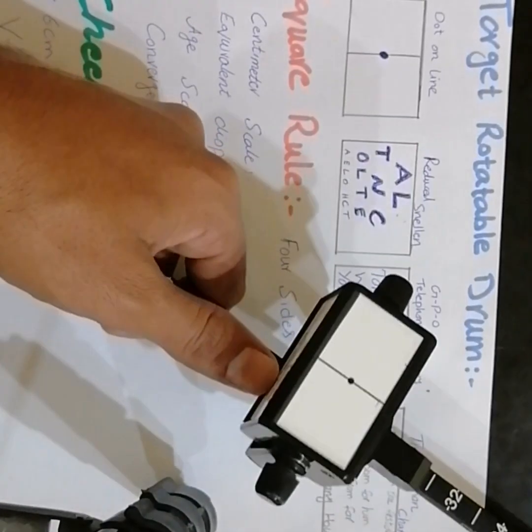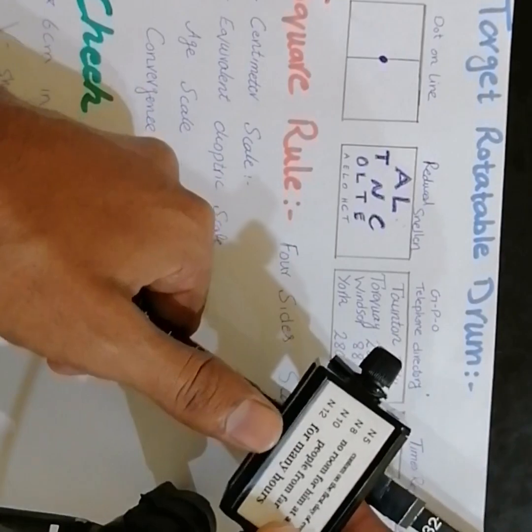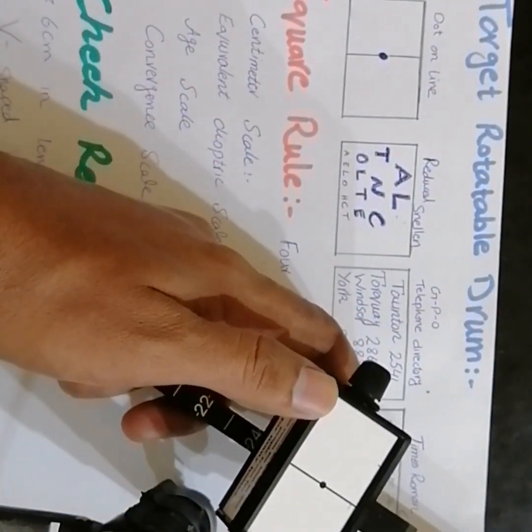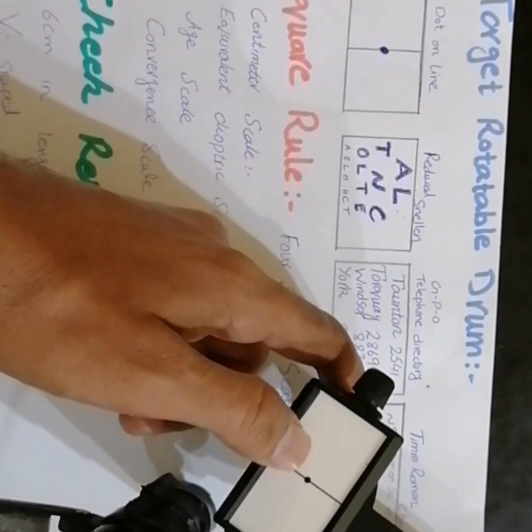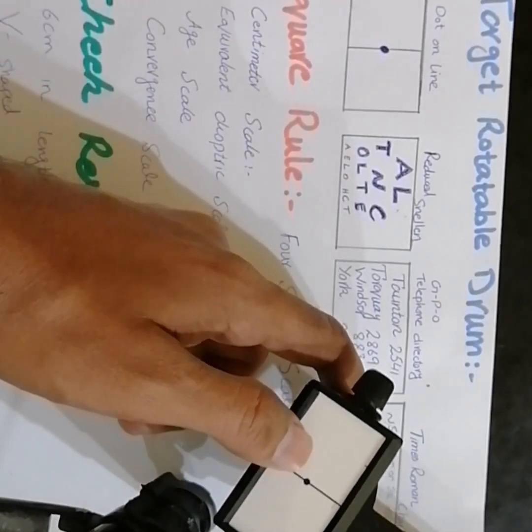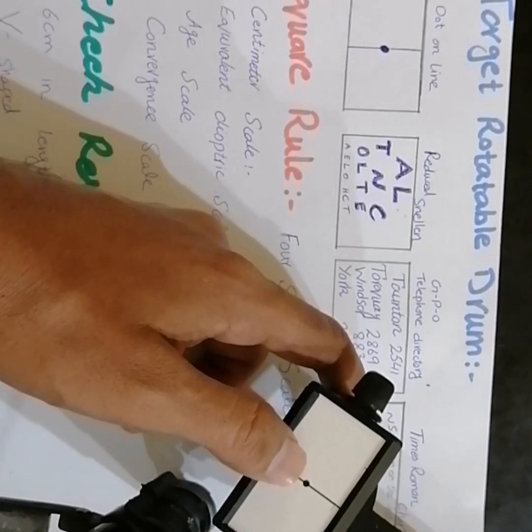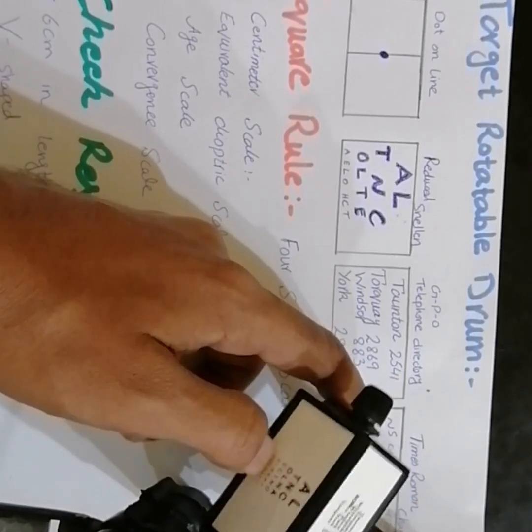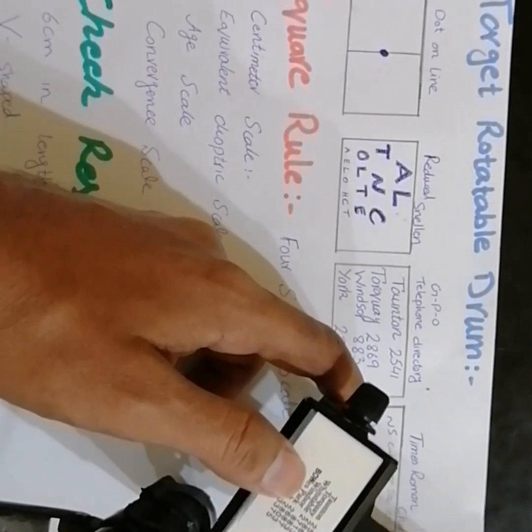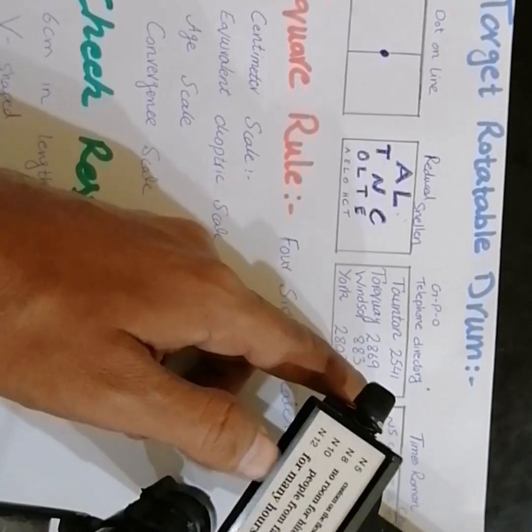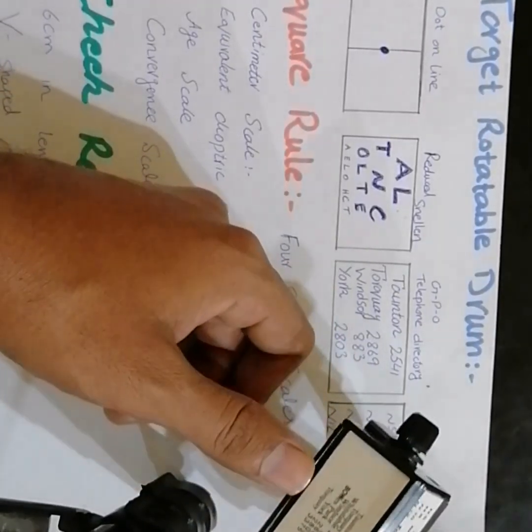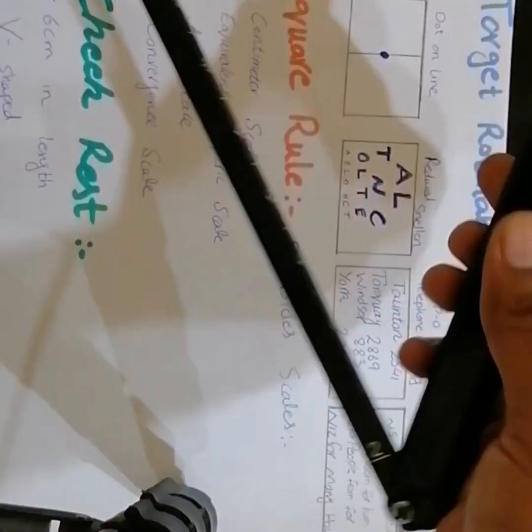To summarize the rotatable target drum: the dot on the vertical line target is used specifically to assess the near point of convergence, while the other three targets — the reduced Snellen chart, the GPO telephone directory, and the near vision chart — are used to assess the near point of accommodation.